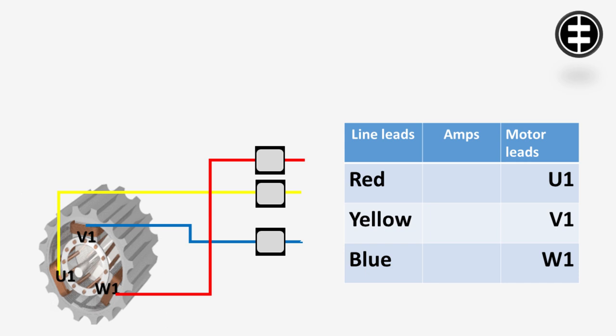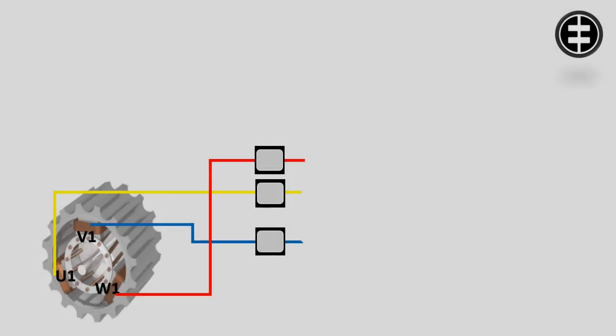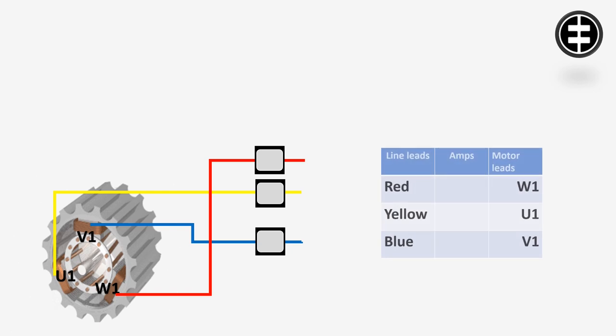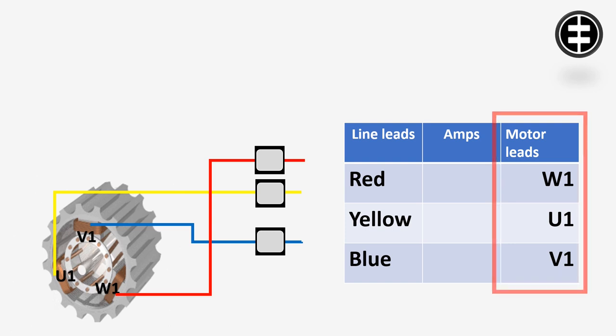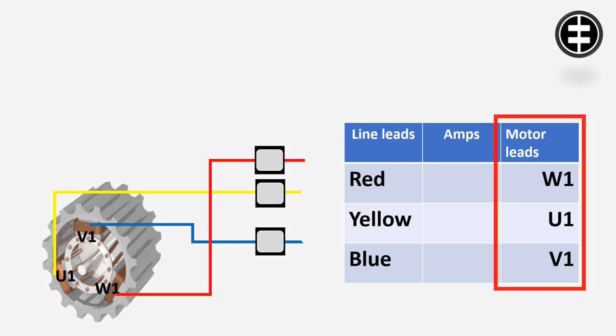Now draw again the table, but this time according to the new connection. So it will be red, yellow, and blue on the line leads side, but on the motor lead side it will be W1, U1, and V1. Now start the motor and measure the three-phase currents and write them all down in our new table.